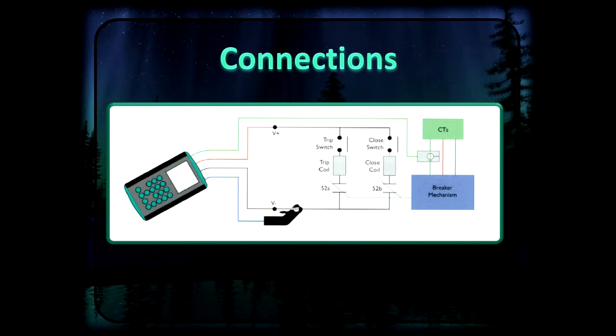So your connections: you have this Profile P2 analyzer, and then your leads come out. You'll hook up to the breaker with 2 leads going to the DC, one to the positive, one to the negative, which is represented in this picture by a red line and a black line going to your DC. Then you have your blue line, which is your amp probe, and that's going to monitor the current as it goes to your coils.